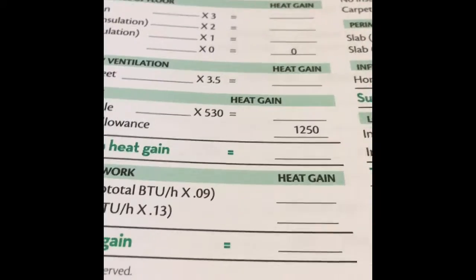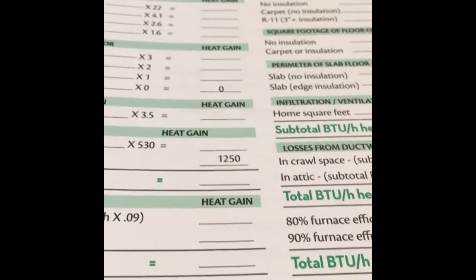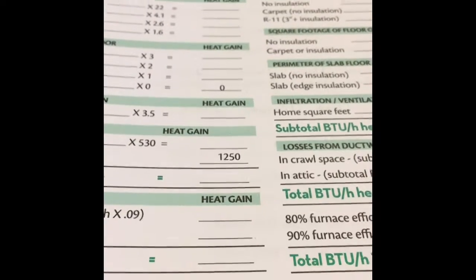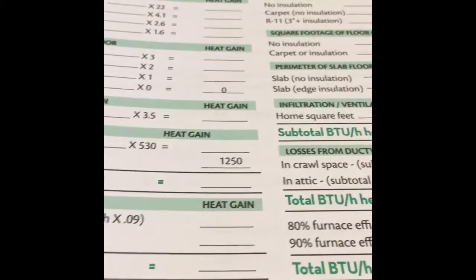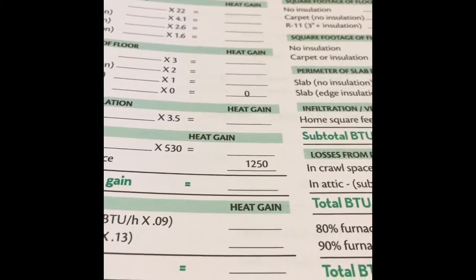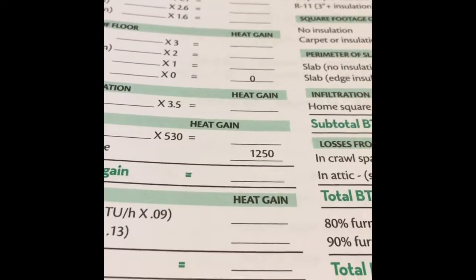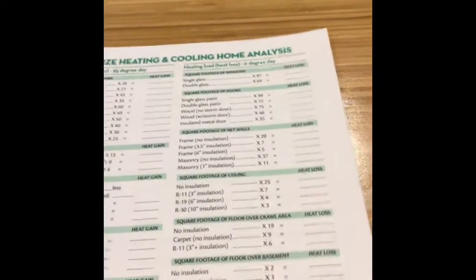Here, this is what's interesting. What your cooling load numbers may end up looking like is, say the total here was 22,000 or 19,000. Remember we looked at the BTUs on an air conditioner in 12s. So if it says something like 19,000, it's probably going to take a 2-ton air conditioner, because remember the 2 tons are 2 12s, which is 24,000 BTU. Maybe this says that it needs 19,000. Well, that's fine. We'll do the 24. And when you do this on a house, you know beyond a shadow of a doubt exactly what the house needs. There's no guessing.